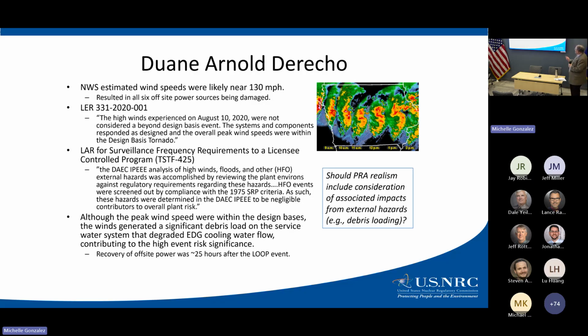What it missed was one of the big contributors to this actual event, which was debris loading on the service water strainers. The high wind event resulted in a lot of debris generation, and that debris found its way to the service water strainers. They didn't lose EDG cooling during the event, but they did need to bypass one of the strainers to maintain diesel cooling water flow. So that was something that wasn't really represented in the PRA. Maybe it's a predictable outcome of this type of event.